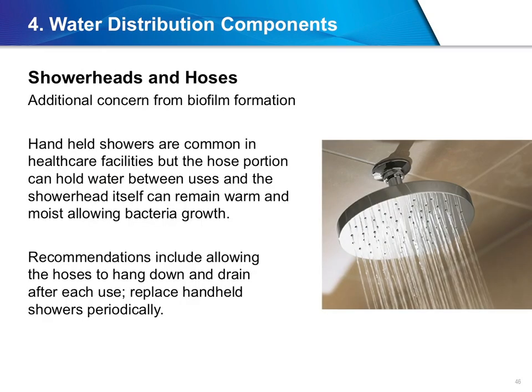Showers and hoses pose additional concerns since biofilm formation can be particularly problematic here. Handheld showers are common in healthcare facilities, but the hose portion can hold water between uses, and the shower head itself can remain warm and moist, allowing bacteria growth. The recommendations here include allowing the hoses to hang down and drain after each use. It is also prudent to replace handheld showers periodically. Point-of-use filters are also a consideration for both faucets and showers.